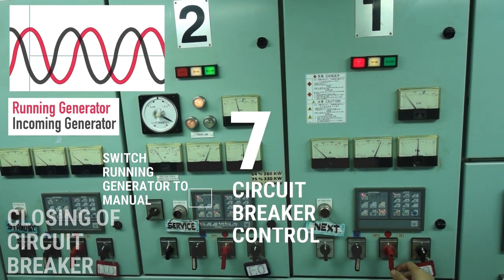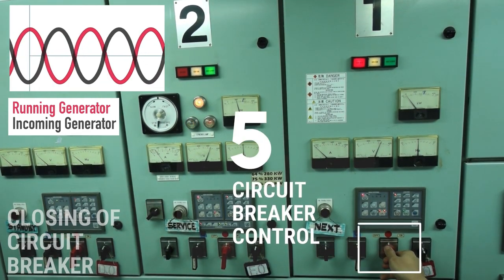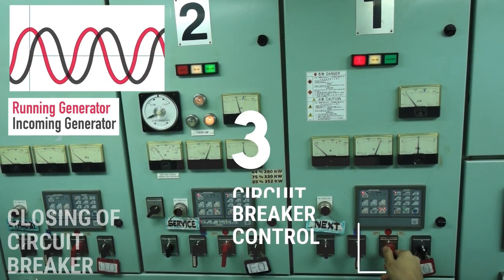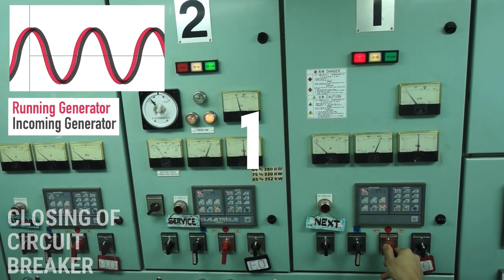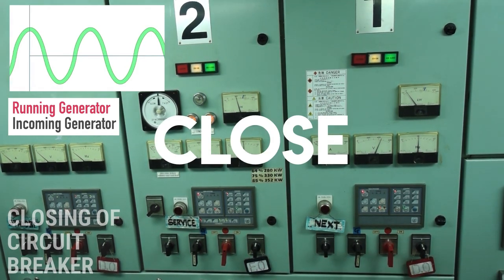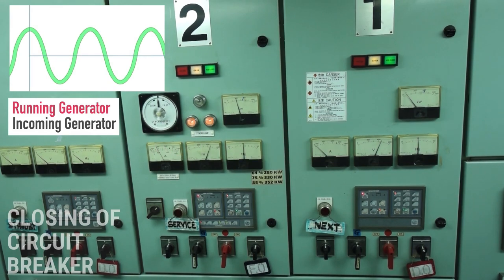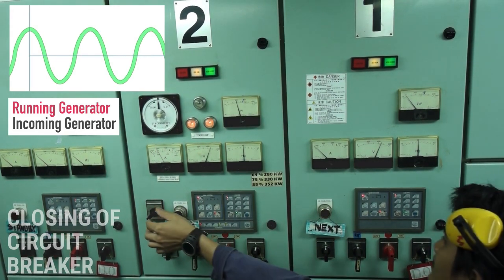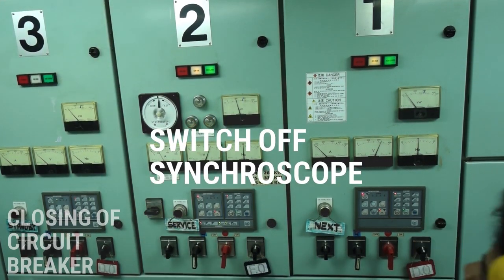Due to the reaction delay of the operator and the time to close the circuit breaker, we normally close the circuit breaker at 11 o'clock. After successfully closing the circuit breaker to the bus bar, switch off the synchroscope.